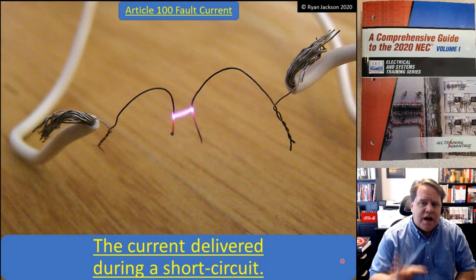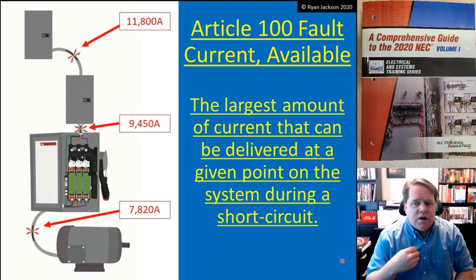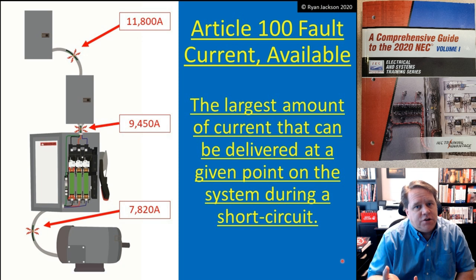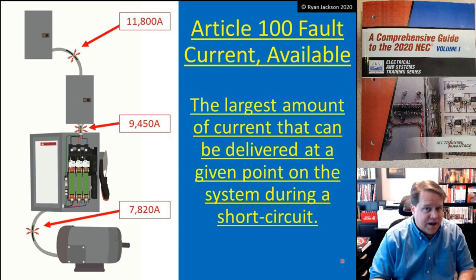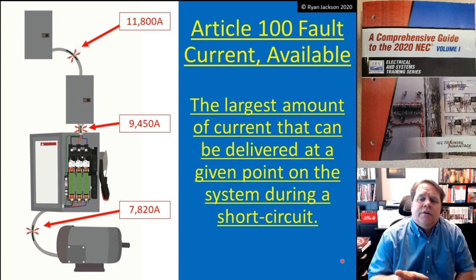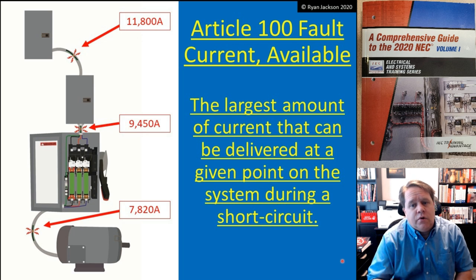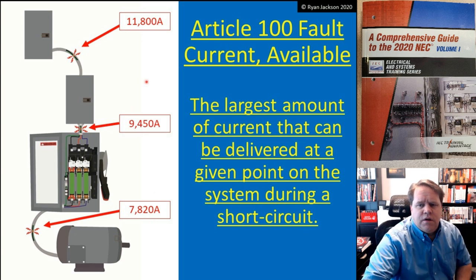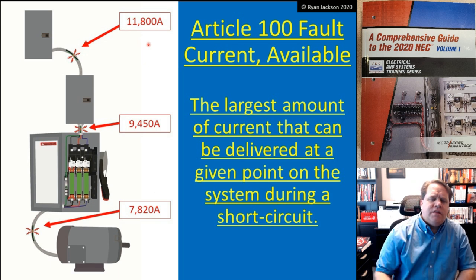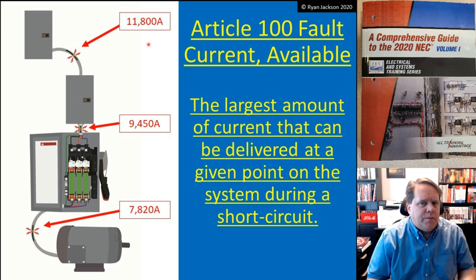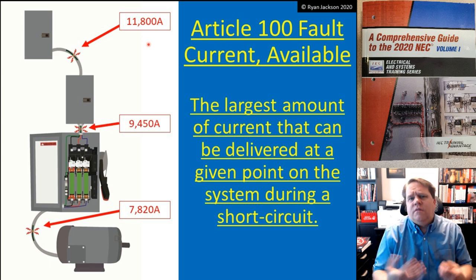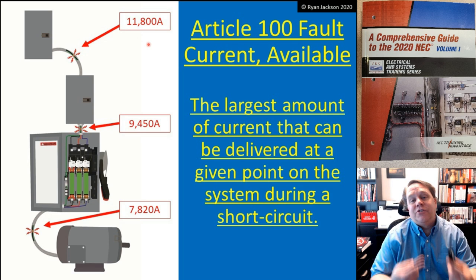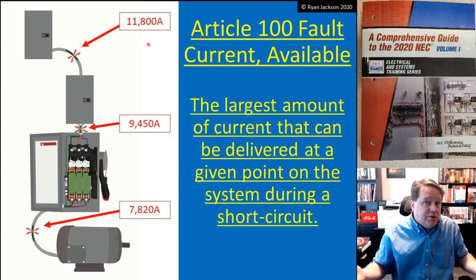So, how much current is flowing? That's the fault current. What is the available fault current? This is something that's been in the code for a very long time but did not have a definition. In 2020 they added a definition, which is the largest amount of current that can be delivered at a given point on the system during a short circuit. One of the things you'll notice is that the available fault current is different throughout the system. When people first learn about interrupting ratings and available fault current, they say, why doesn't the manufacturer mark the fault current? Well, because they can't - because that's installation specific.